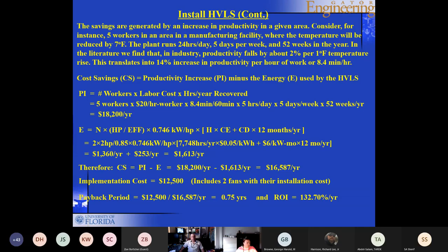Therefore the cost savings will be the productivity improvement minus the energy expended, and you end up with $16,587 per year. The implementation cost is $6,250 per fan, so you're looking at $12,500 for the 2 fans. That's the installed cost, including the installation. The payback period would be the same as we did before. You divide the 12,500 by the 16,587, and you end up with 3/4 of a year. And the return on investment would be 132%.